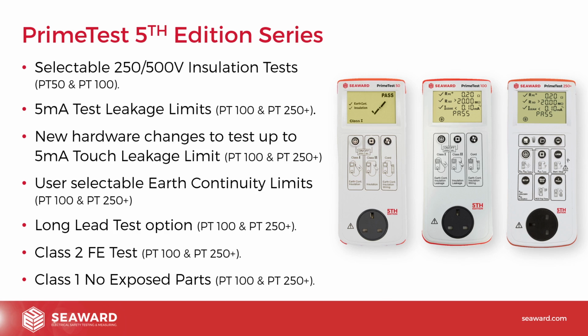Or what we would advise our Apollo users to do is to have a test sequence where you omit the earth continuity test and you record down that no, it had no exposed parts. So you'd record that down in the comments, and then basically that would be a test. It would be the same test as a Class 1 earth continuity test, but you'd omit the continuity test, and you would do the insulation resistance test. So again, we've added that in to give people the ability to do those.